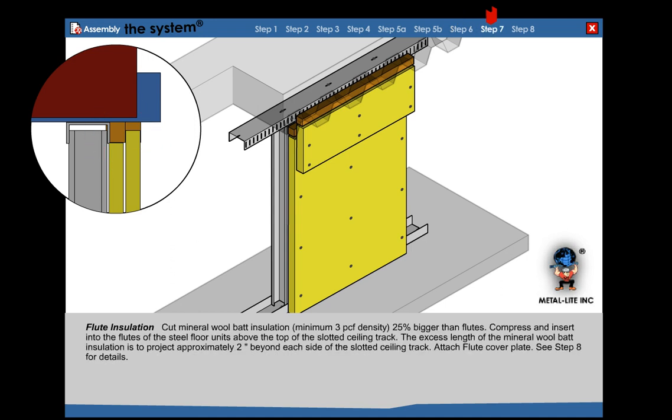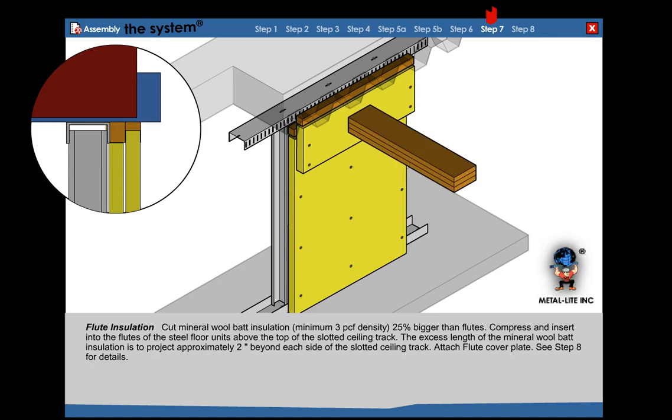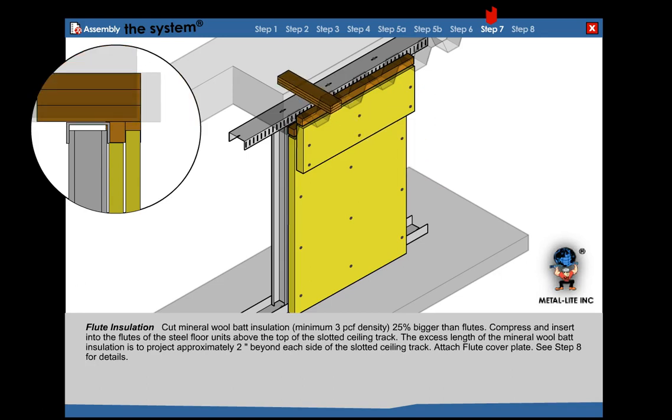Step 7: Flute insulation. Cut mineral wool bat insulation 25% bigger than the flute. Compress and insert into the flute of the steel floor unit above the top of the slotted track. The excess length should project approximately 2 inches beyond each side of the slotted track.